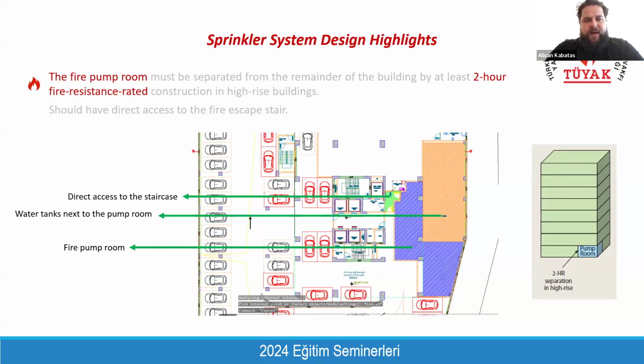That's why we try to provide direct access from staircases, and you need about 150 cubic meters up to 300 cubic meters of water tanks to feed the system. It changes from 60-minute to 90-minute capacity according to the occupancy classification of the building design. But you will have some huge water tanks within your building.